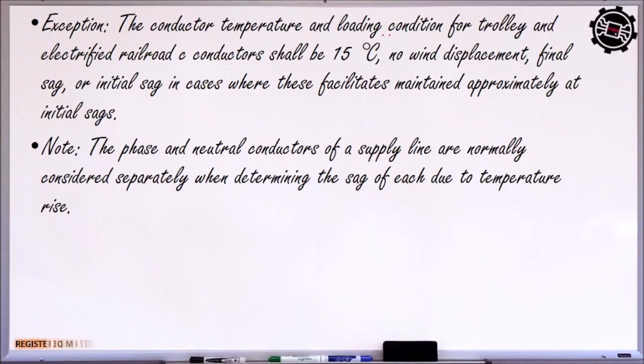Exception, if the conductor and the loading conditions for trolley and electrified railroad or conductor shall be 15 degrees, no wind displacement, final sag or initial sag in cases where the facility is maintained approximately at initial sag. So may note dito that the phase and neutral conductors of supply line are normally considered separately when determining the sag. So magkaiba yung phase, magkaiba din yung neutral. So if you are going to design for the phase conductors, iba yung computation for sag for the phase conductors, iba din sa neutral kasi magkaiba ang kanilang temperature size.